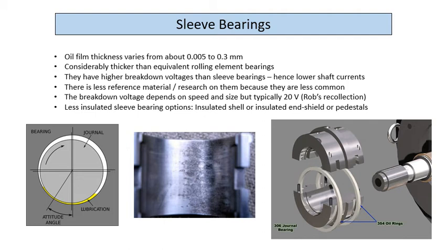Something quite important on big machines, you'll always find that both bearings are insulated, but you short out the drive end when the machine's running. I think a few of you here know the reason for that. If you want to check the integrity of your non-drive end bearing insulation, how do you do it? You measure between the shaft and the housing. If your drive end is uninsulated, you're going to get a short circuit. So the only way you can test is by opening that shorting link on the drive end bearing and checking both. So that's the only reason why it's done like that.